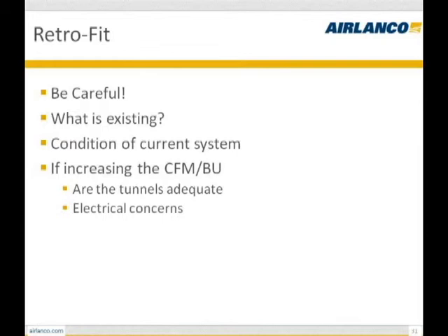When you start looking at the sizing, if a customer calls me, or any of these other aeration companies out there, they can pretty much tell you what size tunnels you need to keep the proper cross-sectional velocities, the proper surface velocities. So just because you want to retrofit a system, sometimes the answer isn't just throwing another fan on there, a bigger fan. A bigger fan may actually hurt the system as opposed to helping it. You might have so much static pressure and so much cross-section velocity that you're not getting a good operating system.